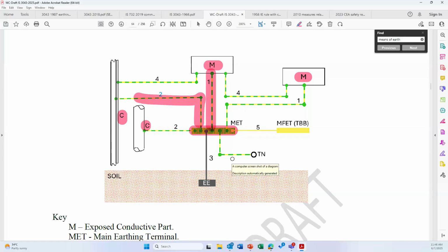This picture was there in the old IS standards, and this picture was also repeating. It was also available in manuals such as the CPWD manual, but we were very rarely looking into this picture and trying to make the correct method. Now here you can see M stands for exposed conductive parts, C stands for extraneous conductive parts. You have an MET, you have a common earth bus bar. The exposed conductive parts are connected to the MET, extraneous conductive parts are connected to the MET. These connections can be made individually or in groups or collectively.